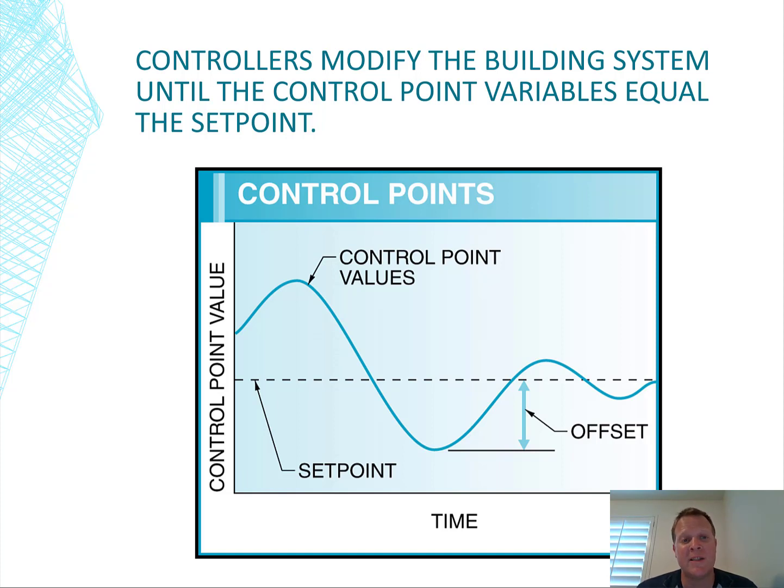But literally, I've seen that setting at the control station with the folks trying to see how this air handler is working, modulating open and close different valves, open and close different dampers, changing the fan speed, all these parameters of the different things. It's usually looking something like what you're seeing right here. It tries to dial it in. It's like, oh, I'm off. I've got too much of this. Okay, let's have the controller go back, and no, wait, we did too much. Let's get it back, and it gets it back. Oh, we went too far.